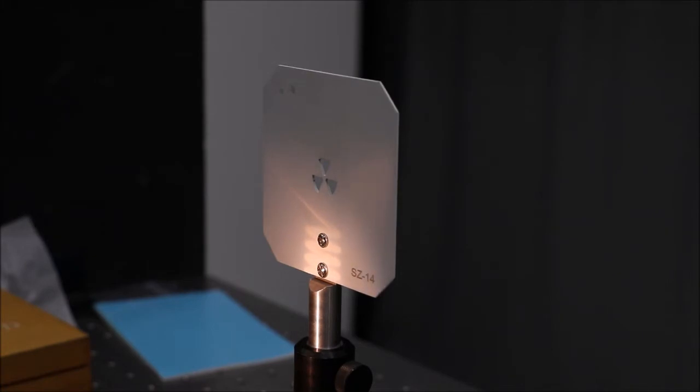Next, adjust the position of the lens side to side, up and down so that the filament image is centered on the triangle pattern.